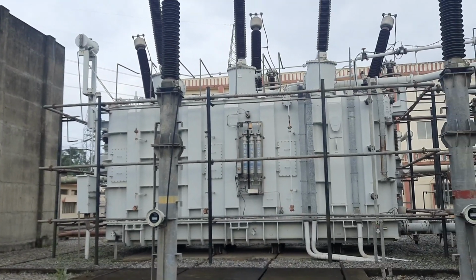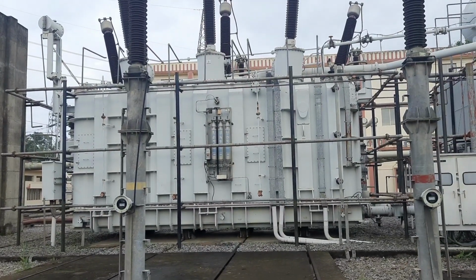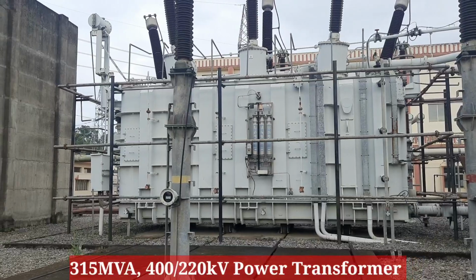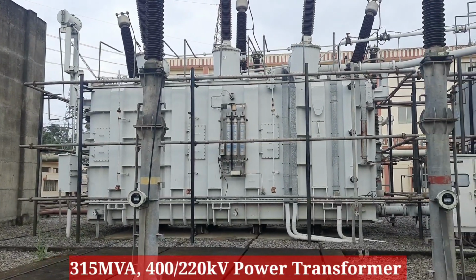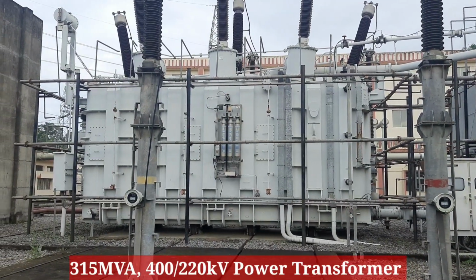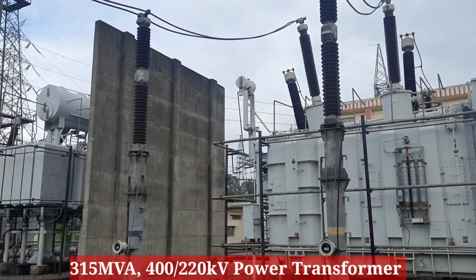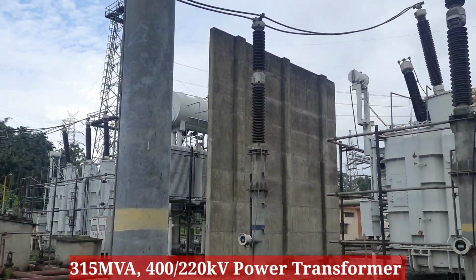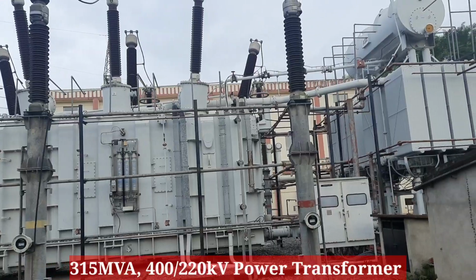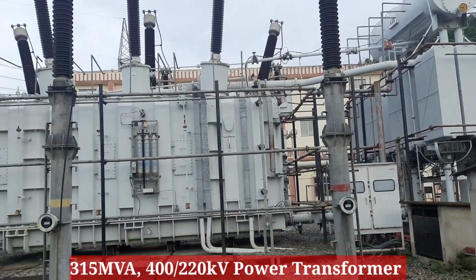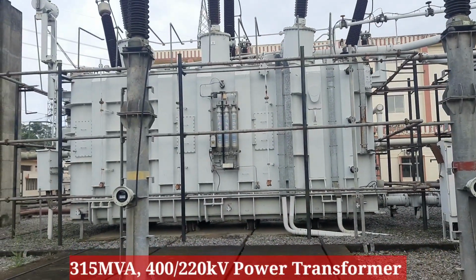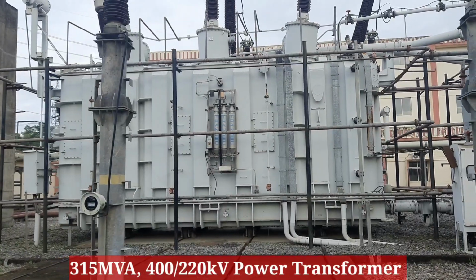Hello everyone, this is a 315 MVA power transformer. It's stepped down from 400 to 220 kV. So these are the lightning arrestors. Also installed are 3 of them, one for each phase, and that is the main tank. In fact, it's quite big because of the size and rating of the transformer.